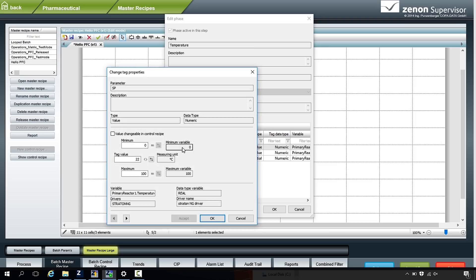When you're designing it, it's a master recipe. And then for quality purposes, you release that master recipe. In production, you execute a control recipe. So this is a template concept — you make an instance of it. Because for example, we could be making chocolate. We have the recipe based on a thousand kilos of chocolate, but today we only want to produce 50 kilos. So we allow certain parameters to change — we still want to make the chocolate in the same way. So if I double click the set point again, I can click here to say 'changeable in control recipe', and then it will be releasable when you execute it.